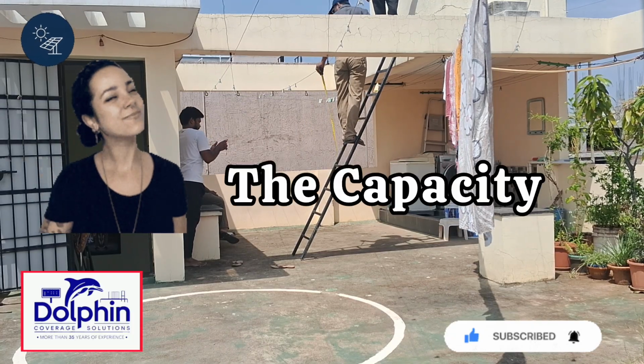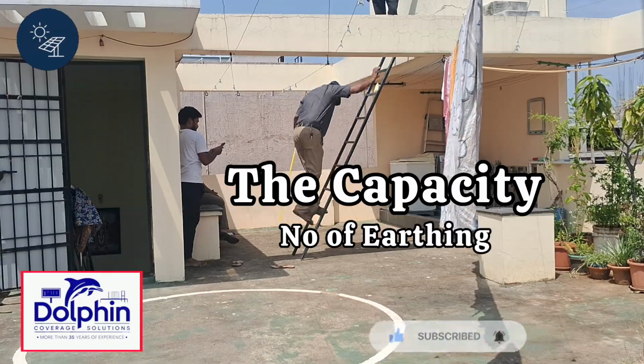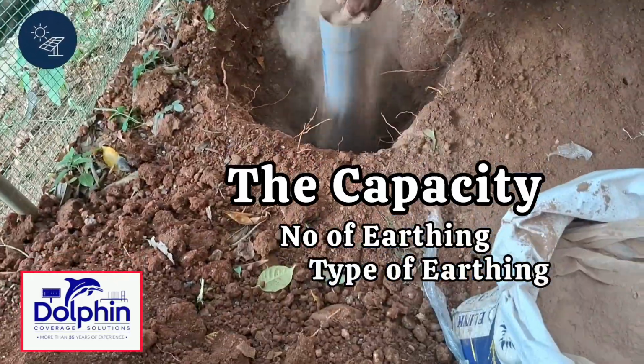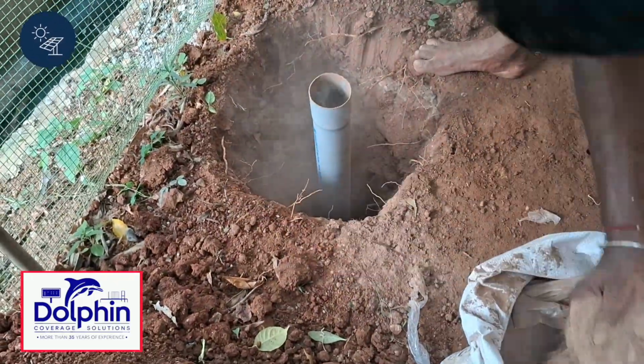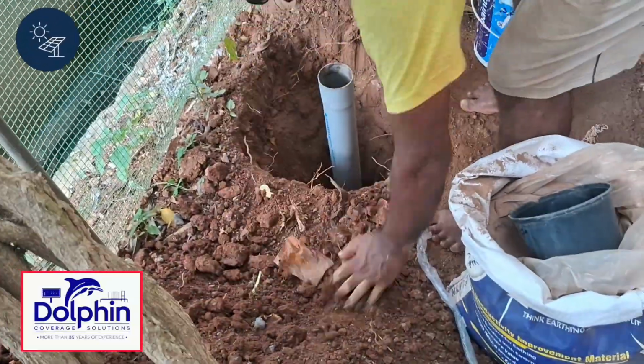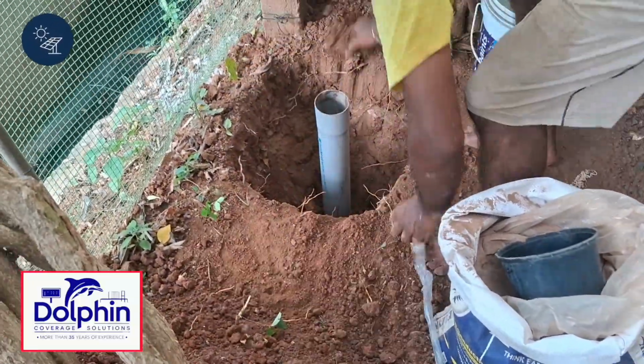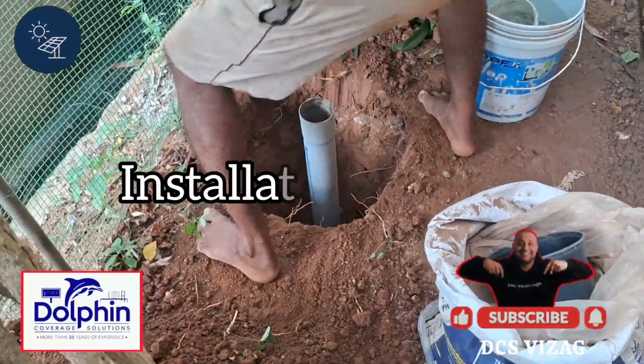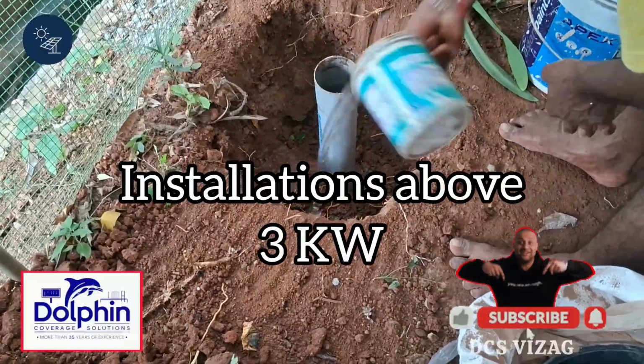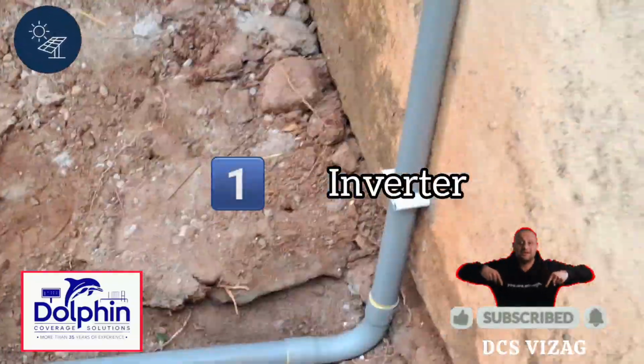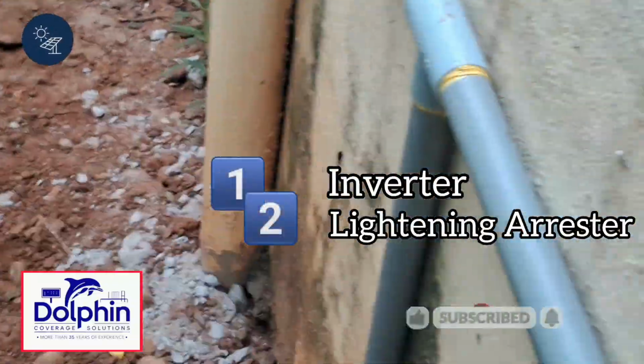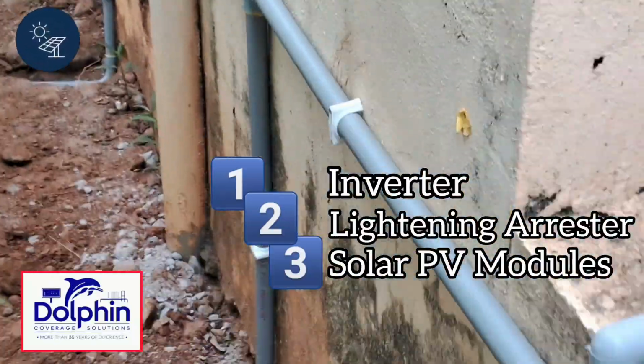Understand the capacity of your solar system to determine the number and the type of earthing points required. For example, 1 kilowatt to 3 kilowatt typically requires two earthing points, one for the inverter and the other for the lightning arrestor. And installations above 3 kilowatts generally need three earthing points: one for the inverter, one for the lightning arrestor, and one additional for the solar PV modules.